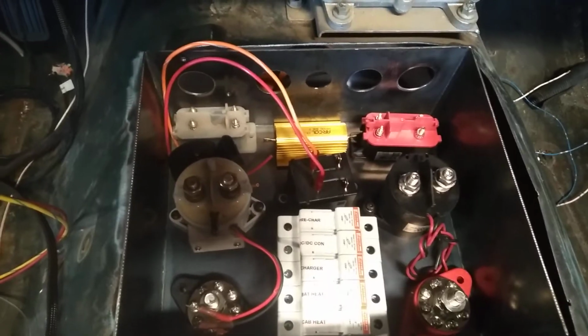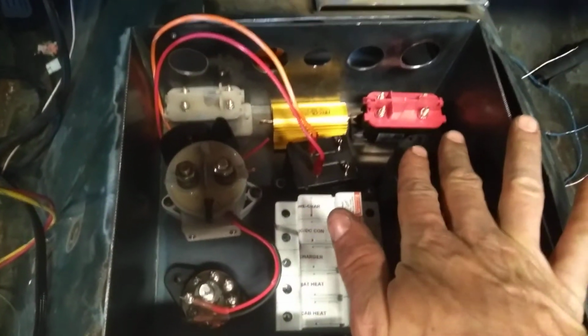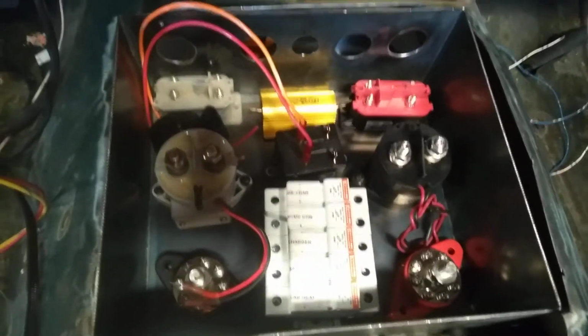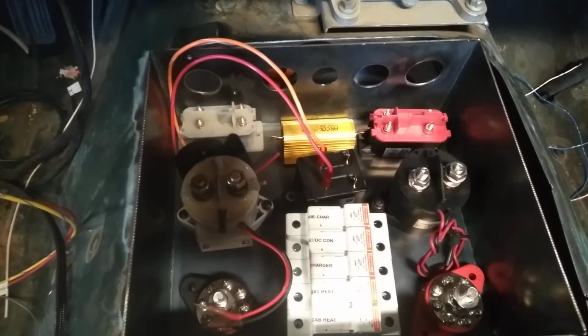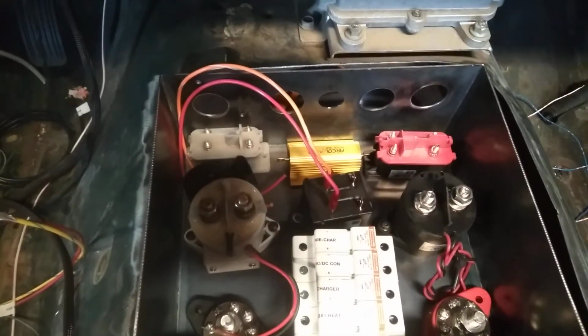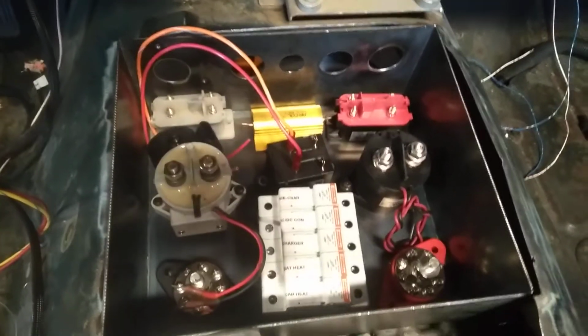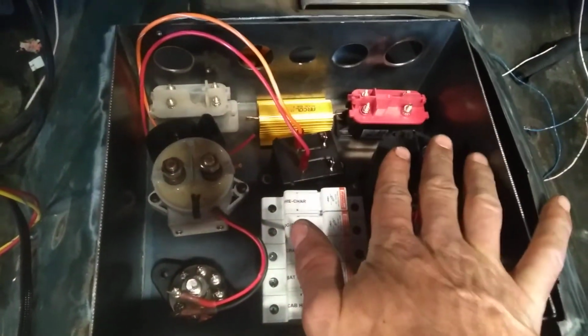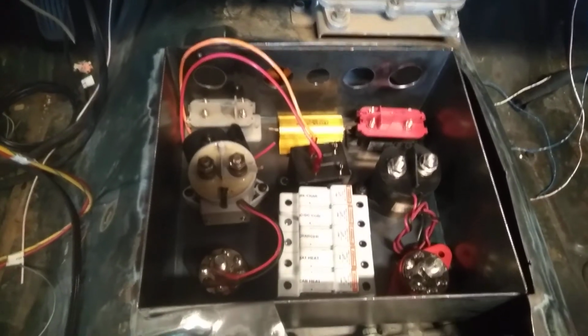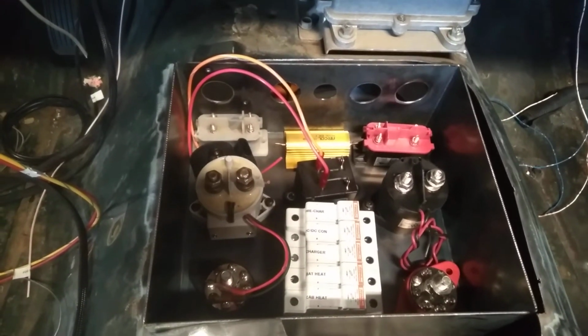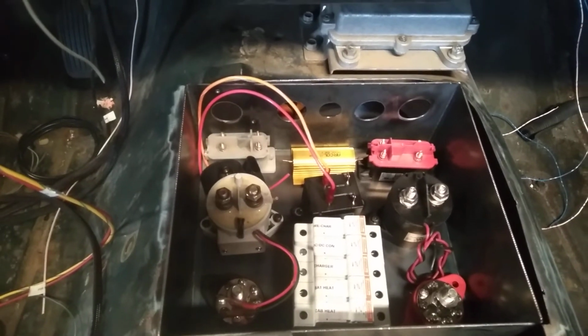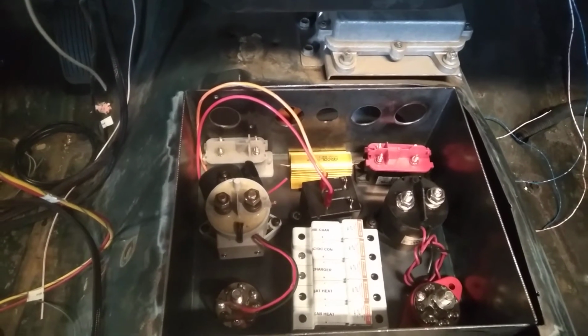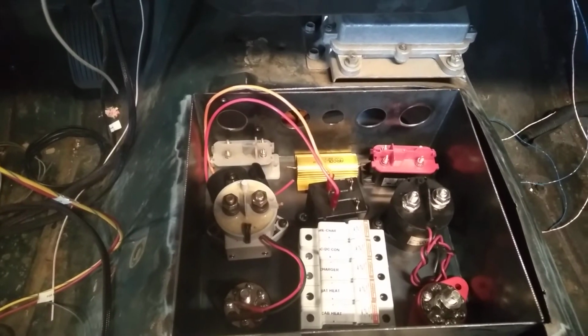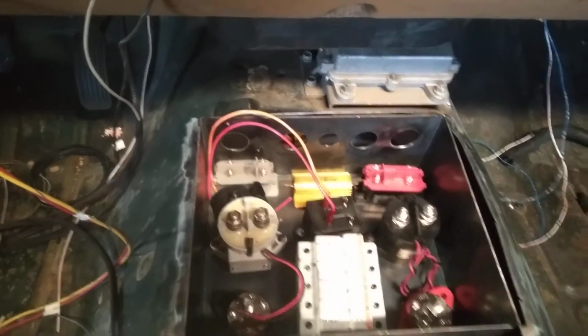Once they are fully charged up, this contactor itself will complete the circuit, and then that relay will just turn off. The little pre-charge relay will turn off. So that's how that works. If you didn't have that pre-charge circuit in there, as soon as this closed, there'd be a humongous inrush of current to charge up those capacitors. You may get away with it once or twice, but it would not last very long. That's a fact. So that's what that is.